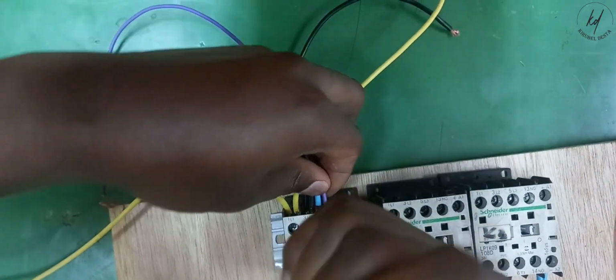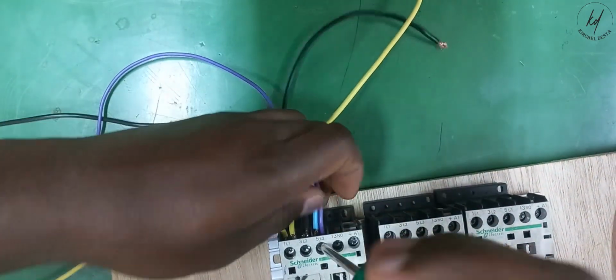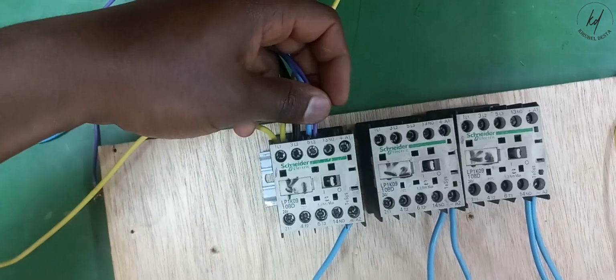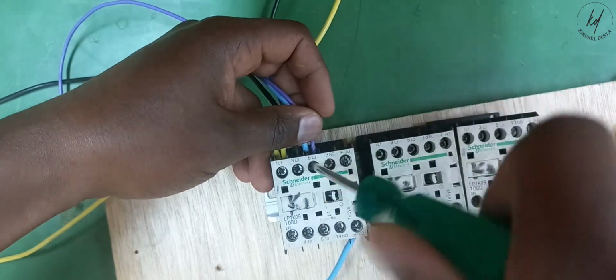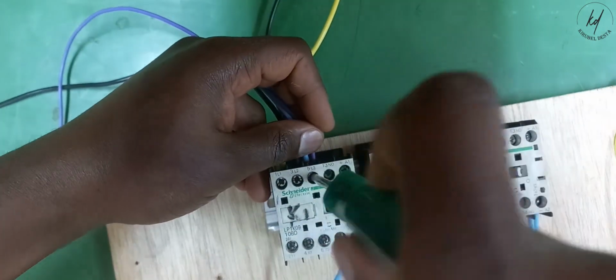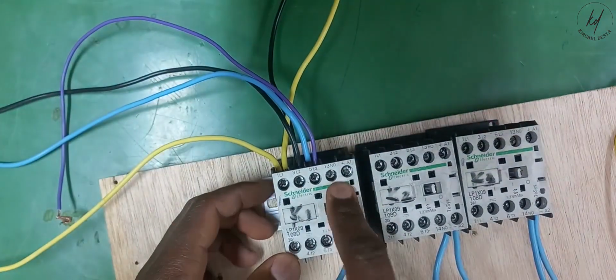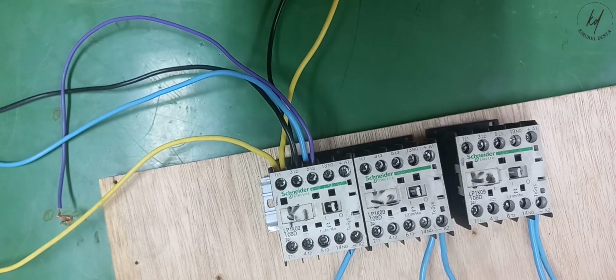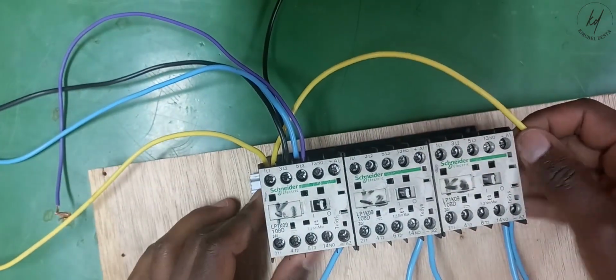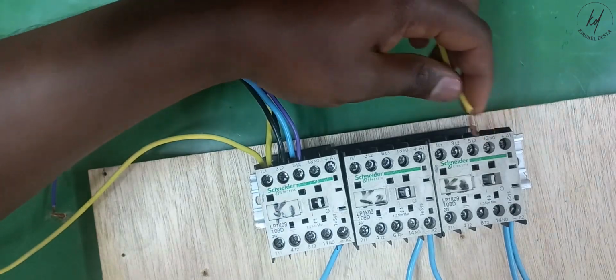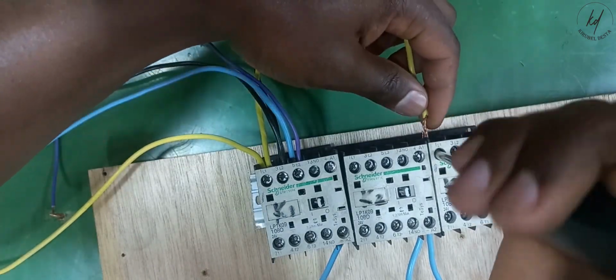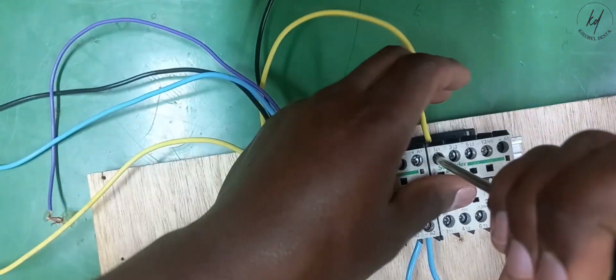Starting and controlling of 3-phase motors using an automatic Star Delta starter. A Star Delta starter is an electromechanical device used to start and control the speed of a 3-phase induction motor. This starter employs the Star Delta method for starting the motor, which involves changing the motor's winding connection from a Star configuration to a Delta configuration once the motor reaches a certain speed.